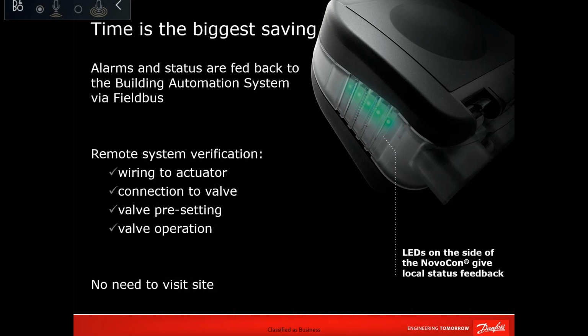So this is a very nice feature because you don't need BMS for that. You can just ask for the actuator to be ordered pre-programmed to maintain delta T in the project. And this is really a simple calculation: 1 degree less on the delta T is 7% of the bill. If you take, let's say, 2 or 3 degrees, that's a huge amount. Now, if you compare the cost of a normal actuator with thermostat to a Novocon pre-programmed to maintain delta T, the payback time is less than 1 year if you consider a standalone.